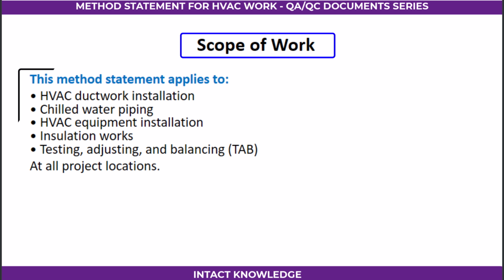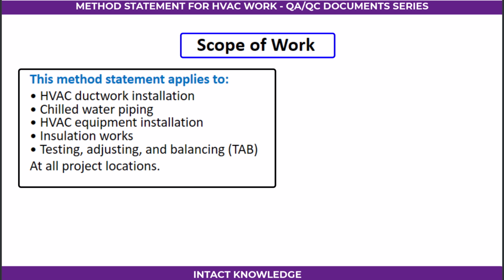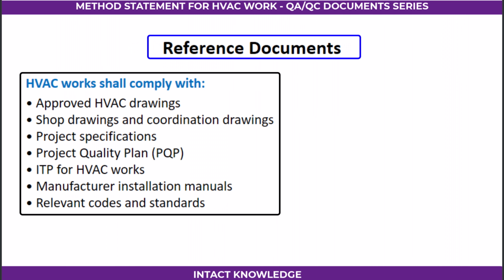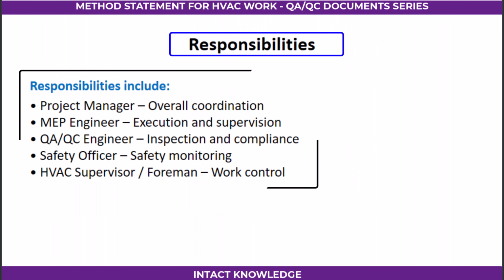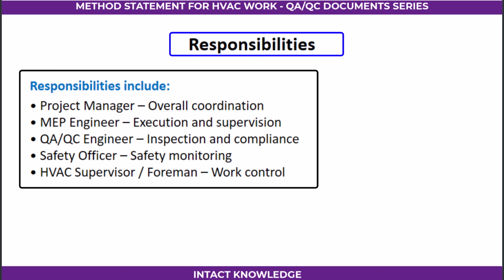Scope of work. This method statement applies to HVAC ductwork installation, chilled water piping, HVAC equipment installation, insulation works, testing, adjusting, and balancing TAB at all project locations. Reference documents. HVAC work shall comply with approved HVAC drawings, shop drawings and coordination drawings, project specifications, project quality plan, PQP, ITP for HVAC works, manufacturer installation manuals, relevant codes and standards. Responsibilities. Responsibilities include project manager, overall coordination, MEP engineer, execution and supervision, QA/QC engineer, inspection and compliance, safety officer, safety monitoring, HVAC supervisor, foreman, work control.